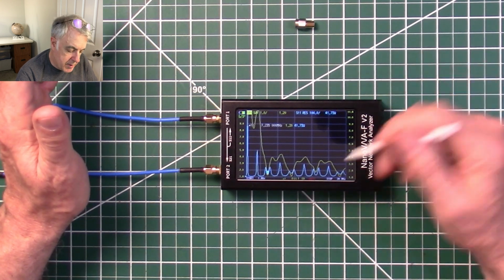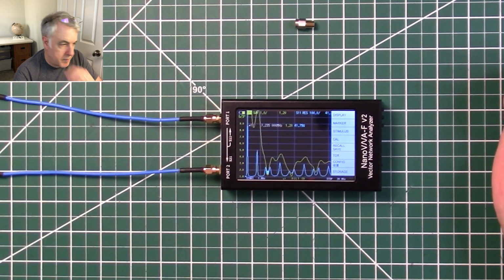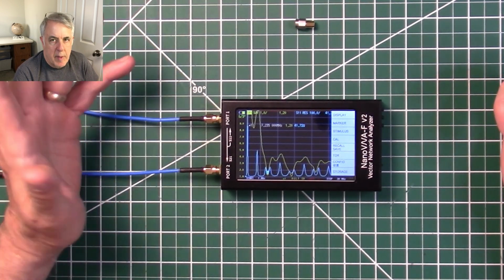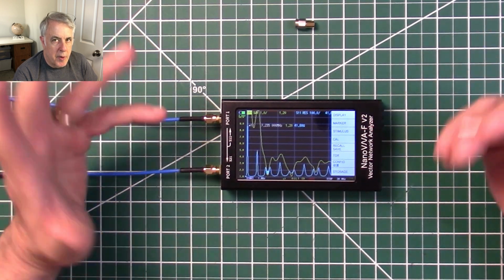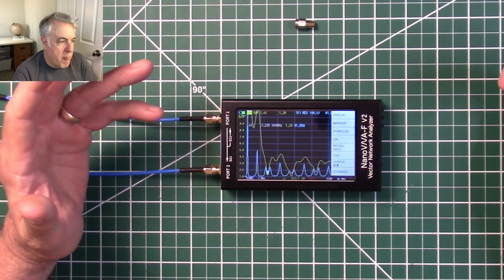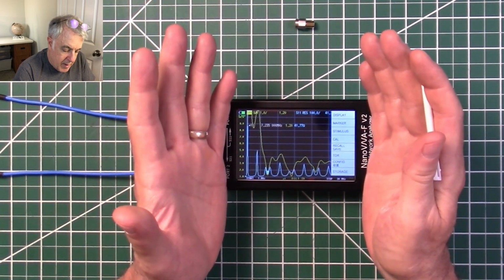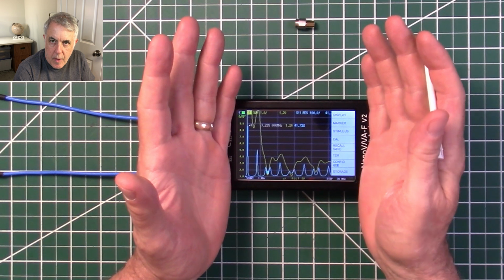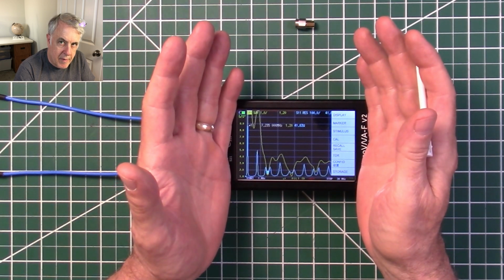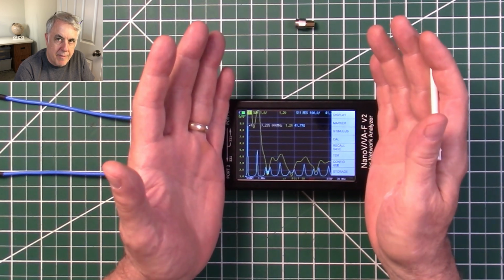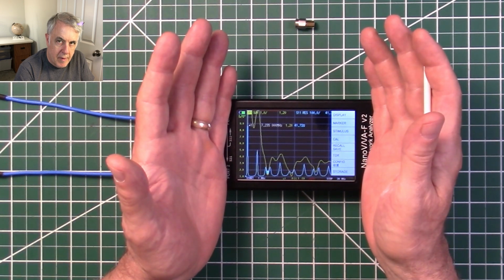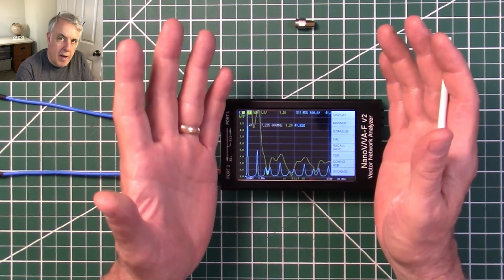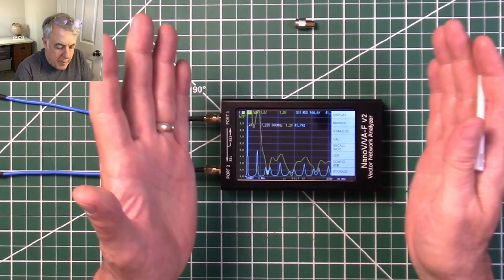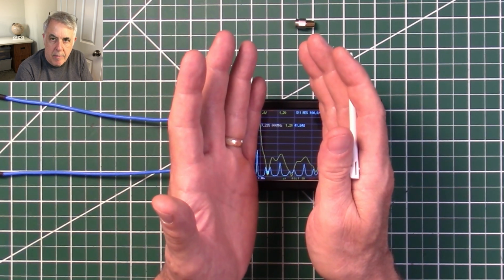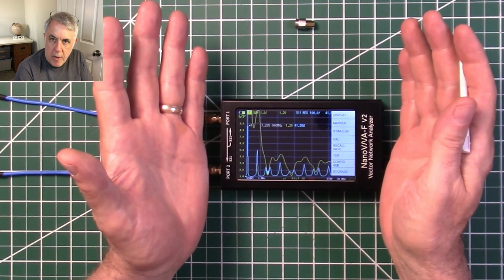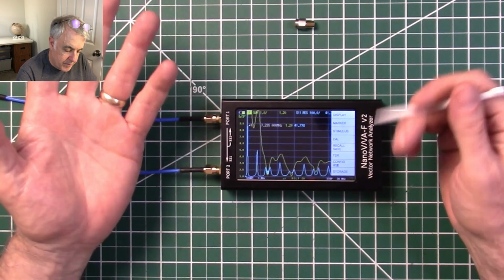How do you change the number of sweep points? Right now we're at 201. Say I wanted to speed it up and only use 101 sweep points. Remember what you're doing: you're swapping speed for detail. If you take a specific frequency range and only divide it up into 101 points rather than 201, you've got half the resolution or detail. So which do you prefer? Do you want a faster scan? The way you can overcome that is to narrow the band that you're scanning. It's up to you. If you want more resolution, you want more points scanning, change it to 201.